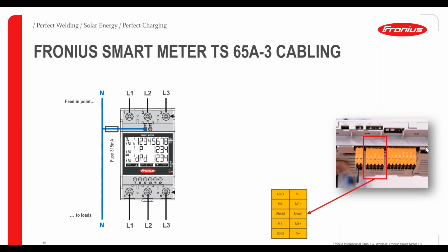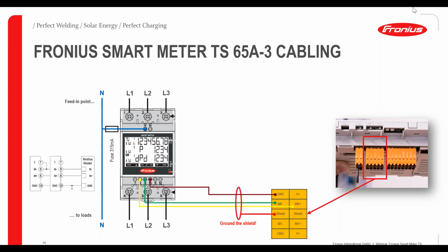On the other side, on the pilot or data communication card of the inverter, as we can see, there are those orange terminal plugs, and on those terminal plugs, we can see our Modbus RTU addressing. And this is the advantage with the new Gen 24 inverters, that we have two Modbus connection areas. So if you have more than one smart meter in the system, if you have, for example, a battery or an Ohmpilot in the system, you can connect them both on the same terminal.